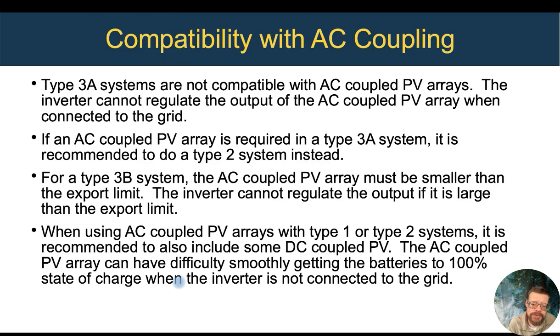The other reason to have at least some DC coupled PV on an off-grid PV system is that if you get into a low battery situation and the inverter shuts down the AC output, then your AC coupled PV array will never turn back on, because the inverter is waiting for the battery state of charge to go up before it turns the AC output on. But that AC coupled PV array, its grid direct inverter, is looking for the grid before it turns on, the grid being the AC output of our inverter.